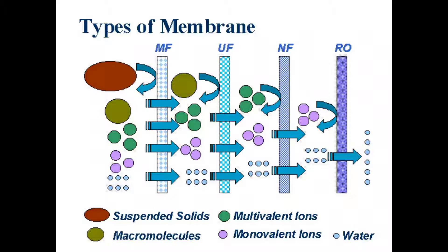In the figure, there are suspended solids, macromolecules, multivalent ions, monovalent ions, and water. In microfiltration, only suspended solids are rejected while macromolecules, multivalent ions, and monovalent ions pass through. In ultrafiltration, suspended solids and macromolecules are rejected while multivalent and monovalent ions pass through. Reverse osmosis rejects all suspended solids, macromolecules, multivalent ions, and monovalent ions — only pure water passes through the membrane.